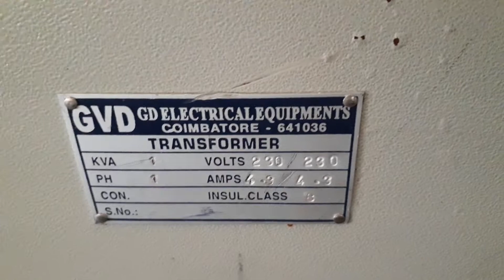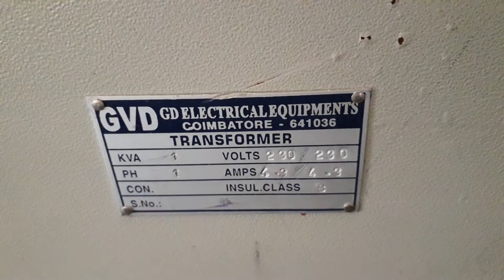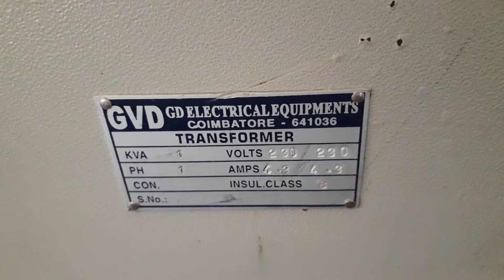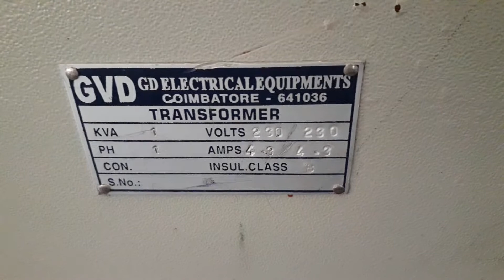Inside you have the primary and secondary windings, and that winding is capable of carrying current only up to 4.3 amperes. If you go beyond that, the winding gets damaged, and sometimes due to the enormous amount of heat it may melt down. That is why, whatever the experiment, you should first refer to the nameplate details of the equipment.